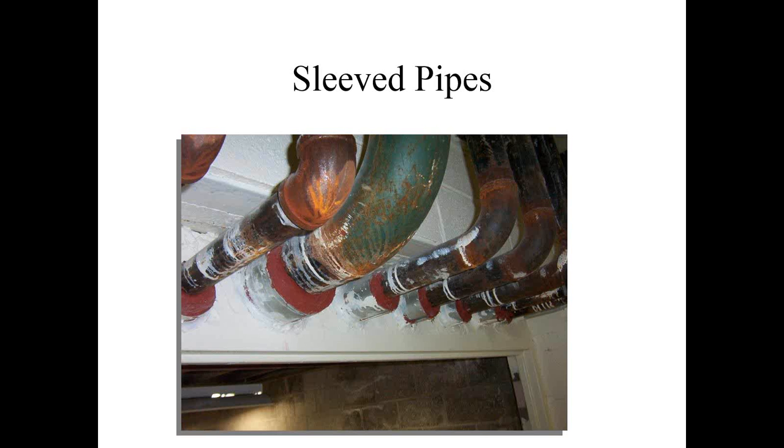That adhesion is critical for the air leakage rating, first of all. If it's not adhered, there's gaps. If there's gaps, there's air. Where there's air, there's smoke. That L rating, whatever it was, may not be appropriate, may not even work because there's no tooling done.